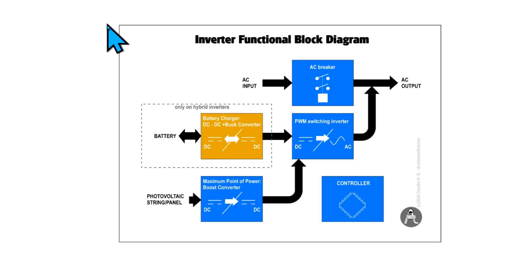This is the functional block of the inverter. Let's start from the AC input and we have the AC breaker. The AC breaker is controlled by the main controller of the inverter and it is used to detach the inverter from the grid when the power on the grid is gone or turned on when the power goes back.